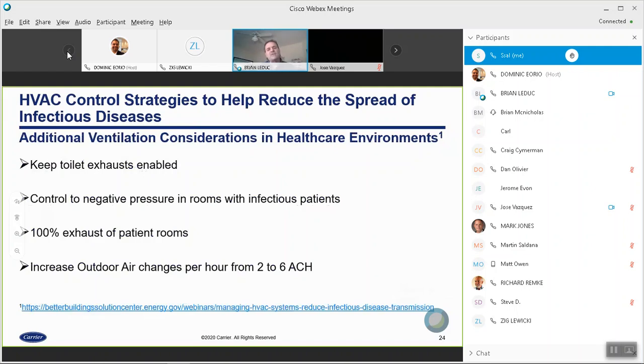Excuse me. Some additional guidance for healthcare environments. Again, this is guidance that was linked from the Better Building Solutions website that's part of the DOE. Make sure the toilet exhausts remain on. Control the negative pressure in rooms with infectious patients. Provide 100% exhaust in patient rooms. Increase the outdoor air changes from 2 per hour to 6. Again, that is going to be challenging. You might be required to provide some additional instrumentation. You'll need to know more about the actual physical design of the facility. But again, these are suggestions from ASHRAE in terms of healthcare environments in particular.